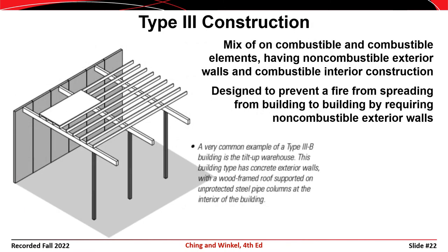Type 3 buildings are constructed from a mix of non-combustible and combustible elements, having non-combustible exterior walls and combustible interior construction. These building types arose in the U.S. at the end of the 19th century to combat the devastating fires that struck congested business districts such as Chicago. The buildings were designed to prevent a fire from spreading from building to building by requiring non-combustible exterior walls. Tilt-up construction with concrete exterior walls and a wood-framed floor supported by steel posts is a modern example of Type 3 construction.